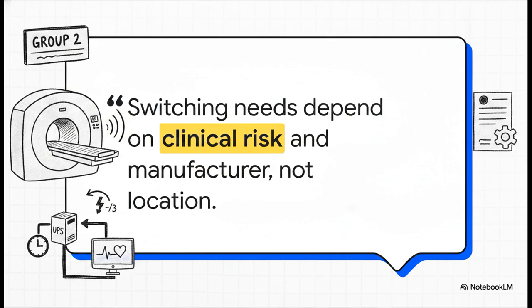You cannot, and I mean cannot, mix up a room's risk classification with a specific piece of equipment's required interruption time. Just because an MRI is sitting in a Group 2 room doesn't automatically mean the whole machine needs a zero interruption UPS. Whether you need that sub-0.5-second rapid switching is entirely determined by the clinical risk of the procedure and the manufacturer's exact specs, not just the label on the door.